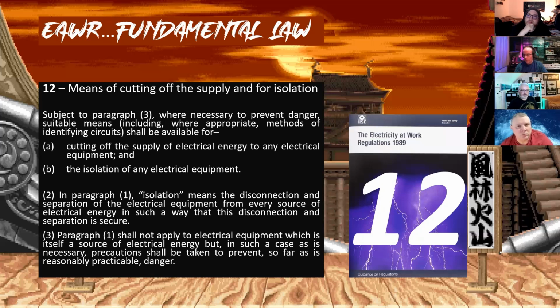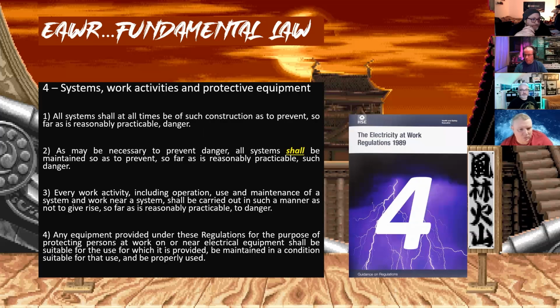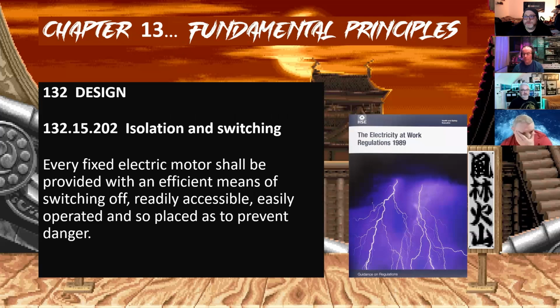Do you think sparks will stop using those metal blocks, the four or eight-way ones? I reckon they won't stop selling them anytime soon, but I reckon they'll have to start mounting them in an insulating enclosure that isn't exposed, unless you have the mains off or something. Yeah, you can get a five-way Henley block, by the way, an insulated one - that's what the DNOs use, the grey ones. You could also use a safe system of work for it, but we'll move on, because that was just one I noted down, even though I got the text wrong, so I apologise.